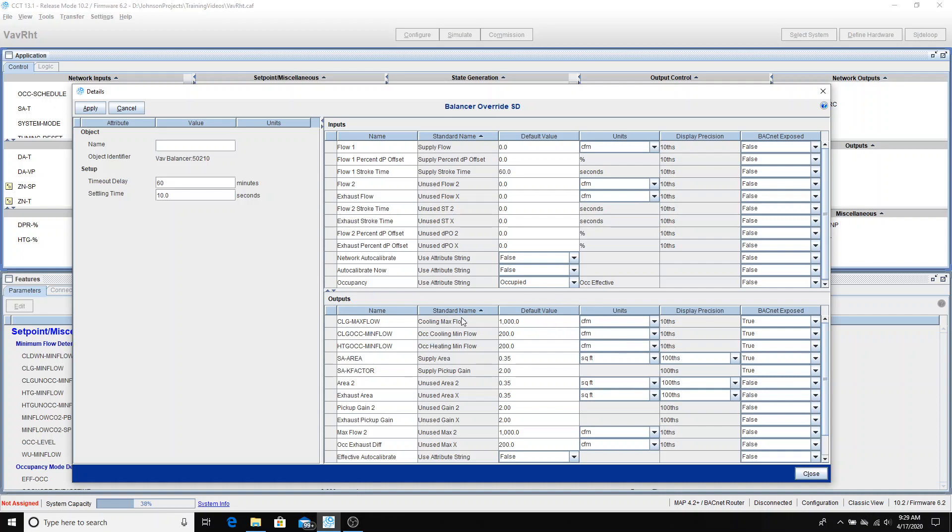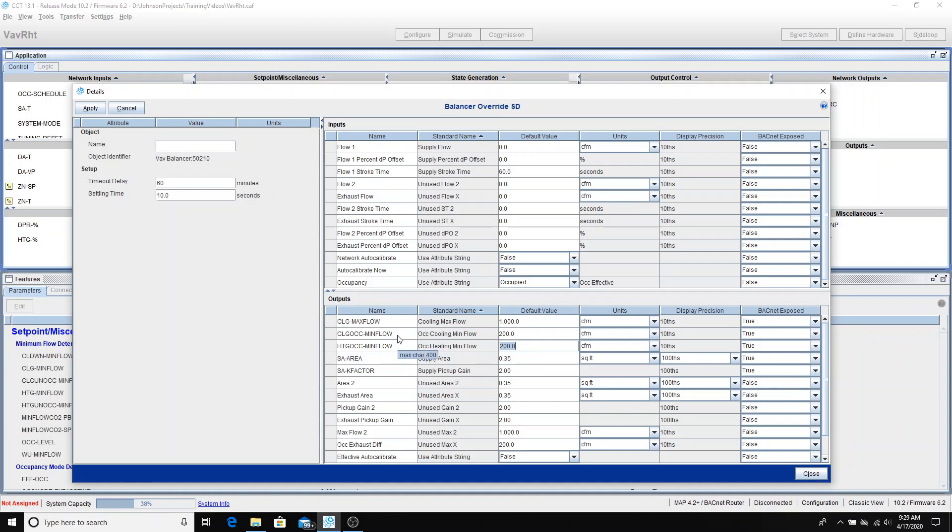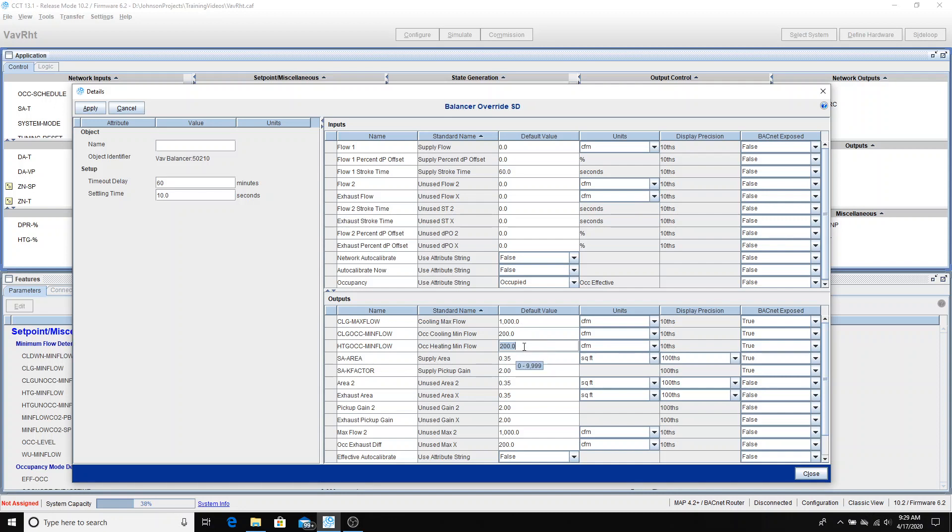I'm going to go to cooling max flow. So we would put the value in cooling max flow. Cooling min flow, we put in the value. Heating OC min flow is usually set to the same value as our cooling OC min flow. However, in some cases, if the air is stratifying near the ceiling and that minimum flow isn't enough to push the warm air down into the space, you may be able to increase the heating OC min flow to something a little higher than that, maybe 50% of our max flow at a maximum, so that we can push that heat down into the space. If you go too high, the air will flow across the coil too quickly, and we won't be able to pick up any heat from that. So you have to be careful about how high you go on that.